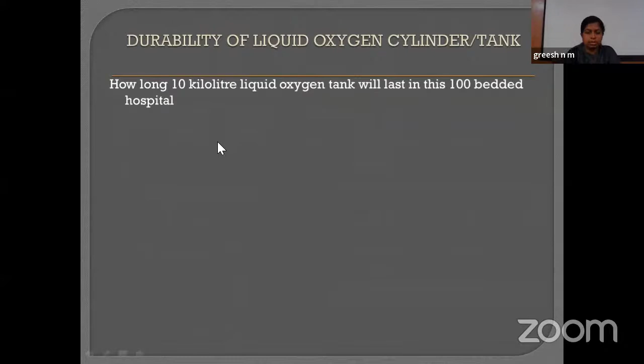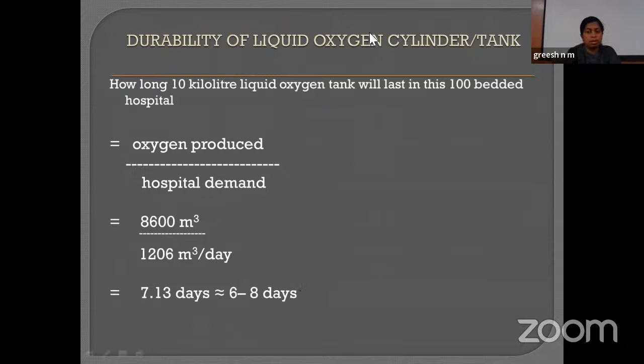Now, how long will a 10 kiloliter liquid oxygen tank last in this 100-bedded hospital? For this, you divide the oxygen produced by the hospital demand. We have already calculated that the oxygen produced by a 10 kiloliter liquid oxygen tank comes to around 8,600 cubic meters. And our hospital demand is around 1,206 cubic meters of oxygen per day. After calculating, it comes to around 7.13 days, approximately 6 to 8 days. So after 6 to 8 days, this tank has to be refilled.